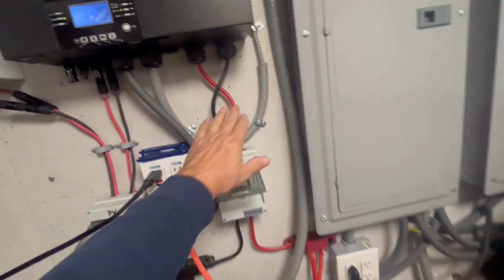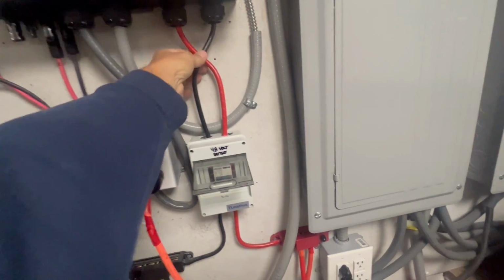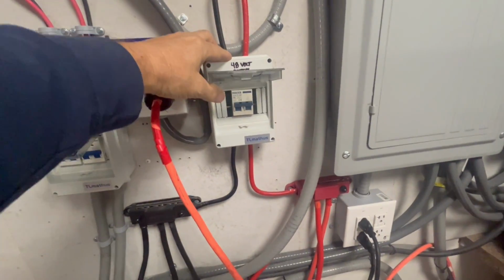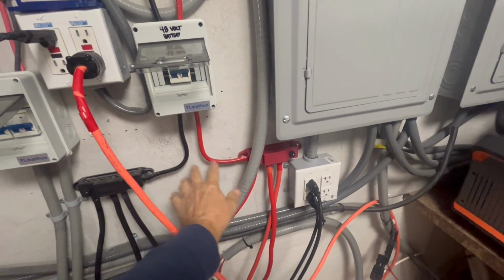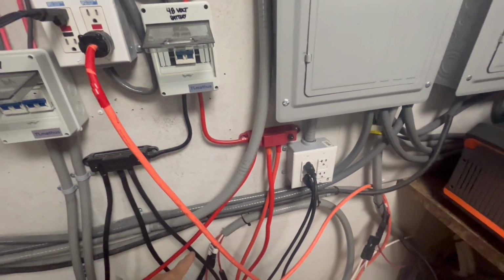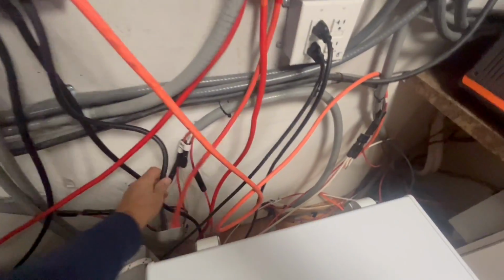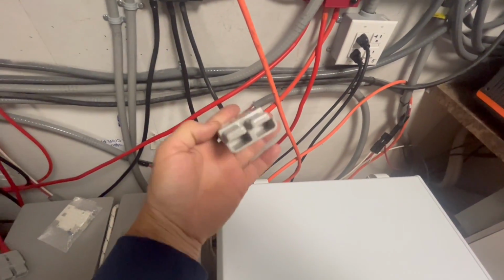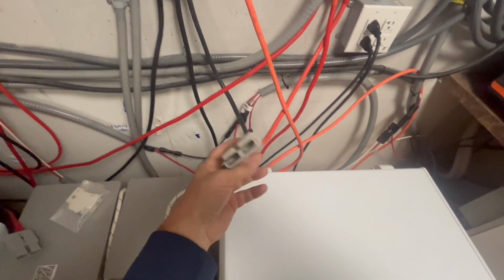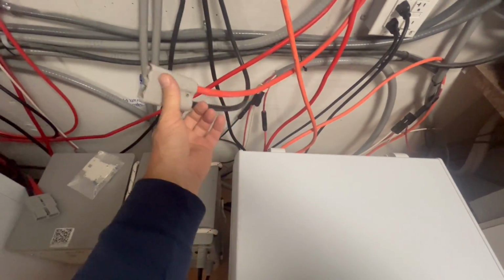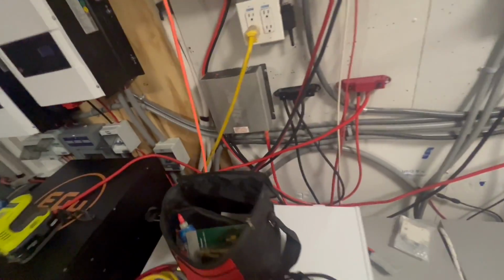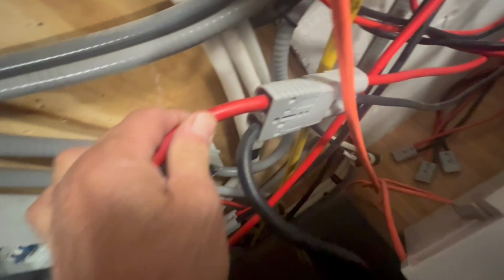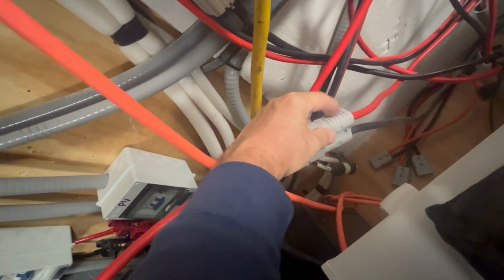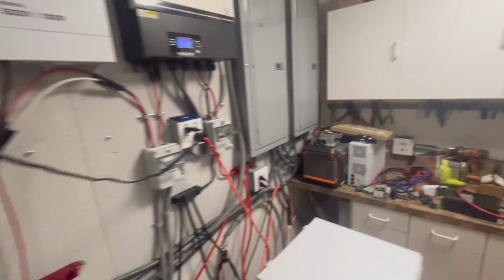Your battery bank comes out of your inverter into a DC breaker, and from the DC breaker it goes to bus bars, and from the bus bars down to the battery banks. On these, I have Anderson 175 amp quick disconnects connected to hook up my battery. Like over here, my battery connects from here, and this goes right there - this part goes up to this, or over to this bus bar, and then up there.